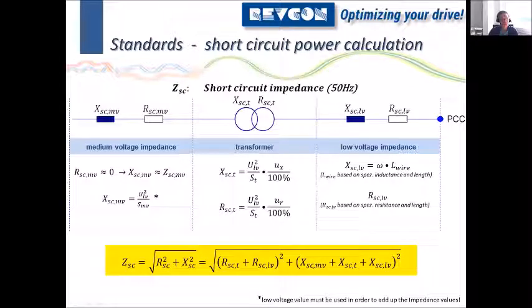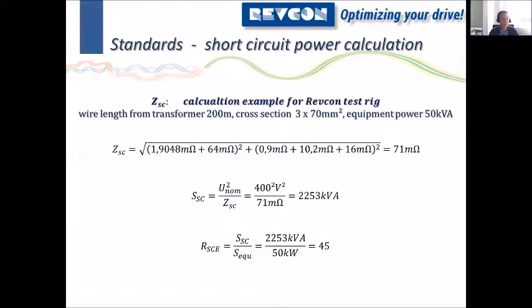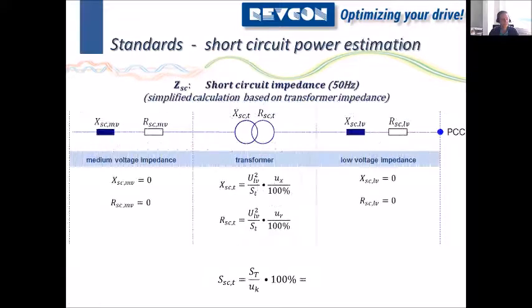At least from my experience, you will never get this information from the customer, because if the customer knows, he might know his medium voltage, his low voltage values. He can know the length, and maybe he knows what kind of material is used, and then you can calculate. But then you get to the transformer, and that's already tricky to get the good transformer values. And when you get to the medium voltage impedance, you normally don't get anything, at least not from the customer. You can get some information from the energy supplier. Kind of a long story short, to get these values is not really reasonable, not really possible.